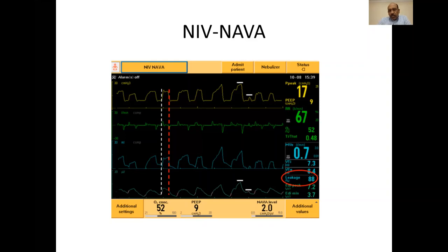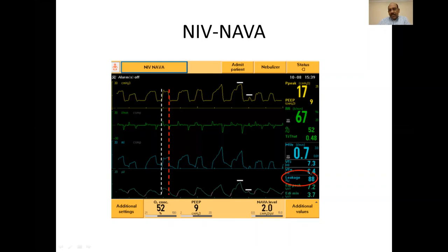This is a screenshot of NIV NAVA. The top wavy line is airway pressure in yellow color. The second wavy line is flow in green color. The third wavy line is volume in blue color, and light green is the EDI signal — the electrical activity of the diaphragm. If you look at the white dotted vertical line, this is the beginning of the inspiratory effort from the patient, and you can see the mechanical breath pressure starting at pretty much the same time. At the red dotted vertical line, as the respiratory effort ends going into expiration, the mechanical breath is also terminated. Even though the leak is 88%, the synchronization is really perfect — and that's the beauty of NAVA.